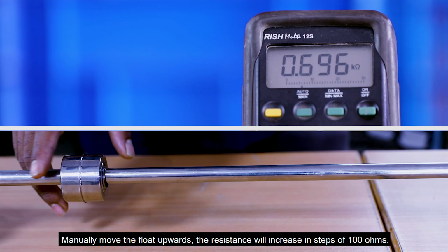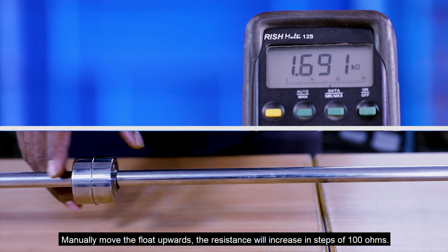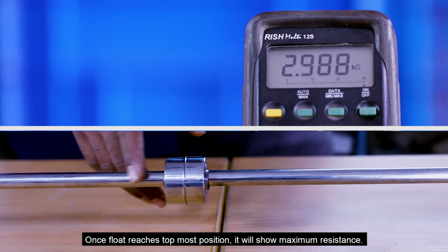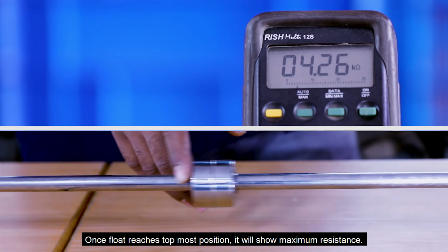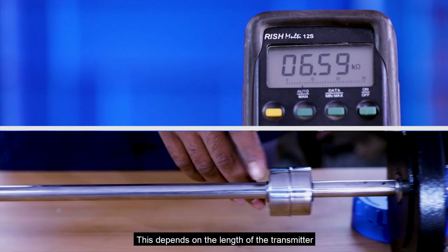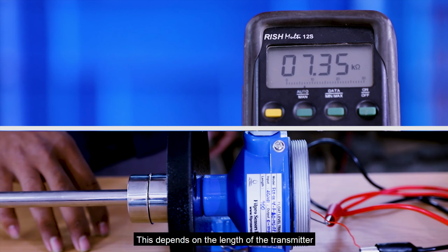Manually move the float upwards. The resistance will increase in steps of 100 ohms. Once the float reaches the topmost position, it will show maximum resistance. This depends on the length of the transmitter.